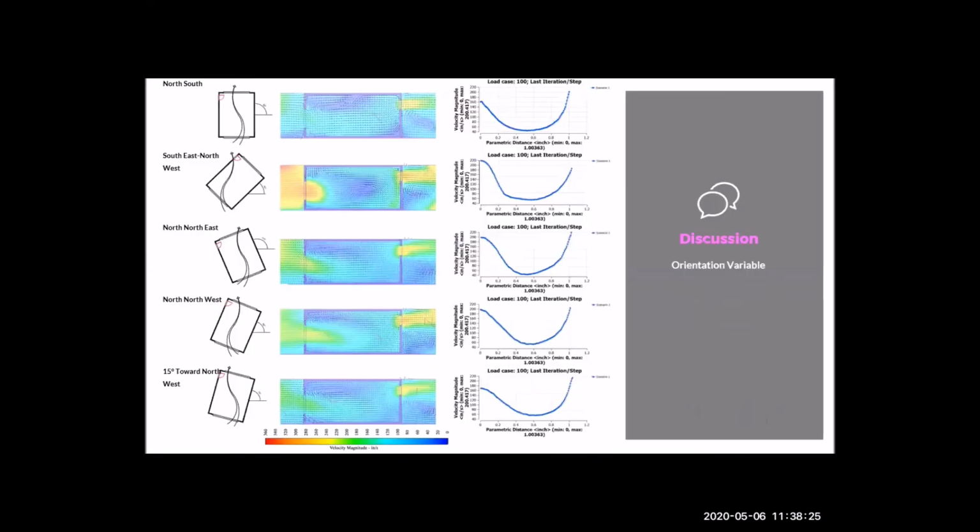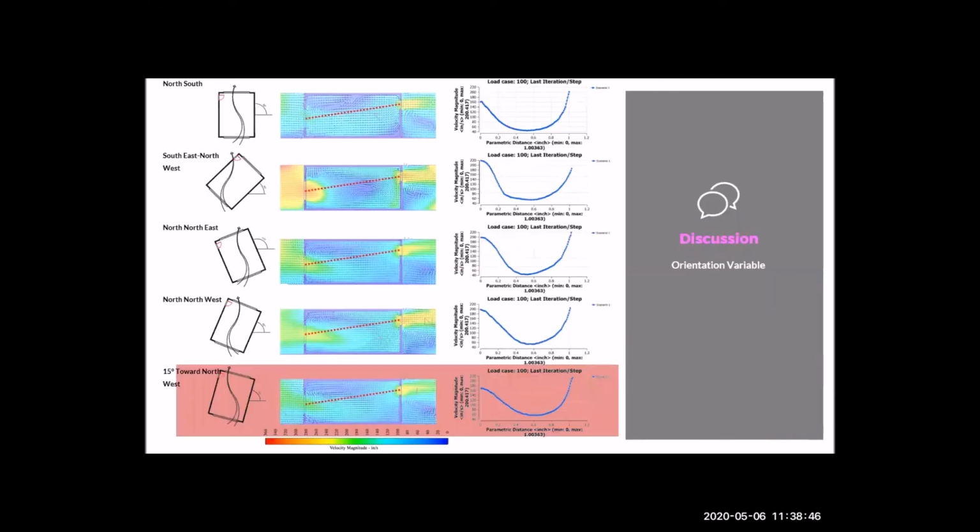Having presented findings, comparison is necessary. This figure clearly displays the difference between velocity and wind vectors. Based on the literature review and background studies, a magnitude of 70 inch per second has the best impact when directing wind through an indoor space. In fact, ASHRAE states that 7 inch per second to 78 inch per second is the optimal range of indoor air velocity.